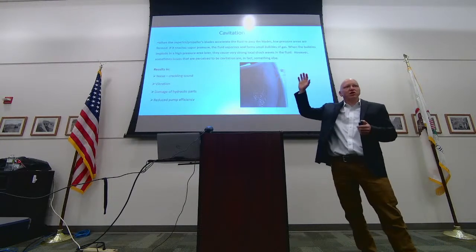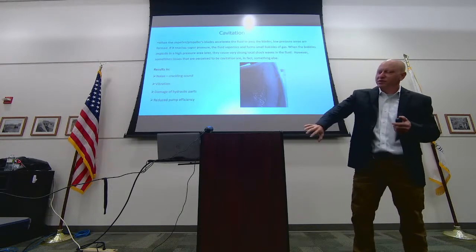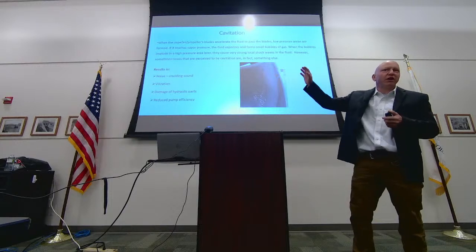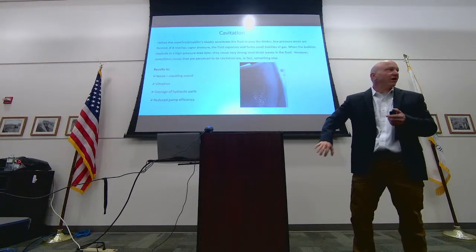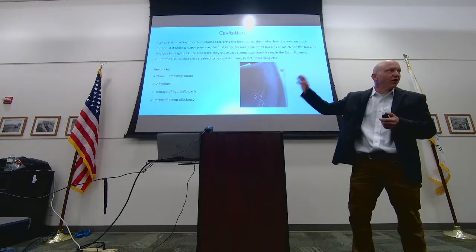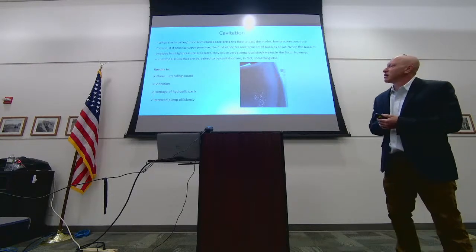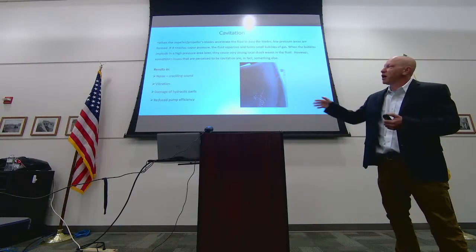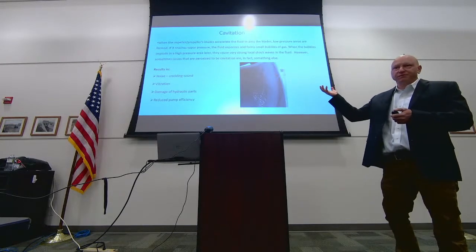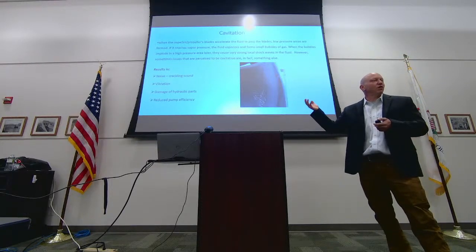Instead of being a vibration, on this make-believe pump here, down here's the volute. Here's where I felt the vibration, not up here in the bearing. And the heat was down here. Cold water, but I'm starting to feel heat down here, not up here. Now we found that issue early on because the pump was tripping out from over temp. So that heat was traveling up the pump, even with a cooling jacket installed, and was tripping out the over temp sensor on the pump.